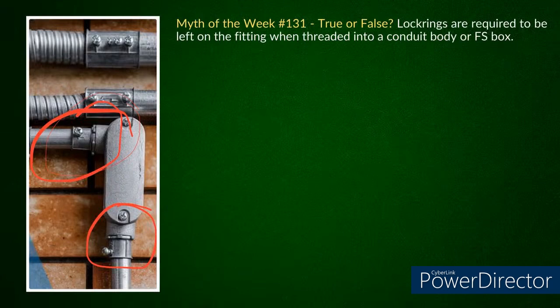And oh yeah, I don't think you'd be passing that over there in Grapevine. No, I can already tell you I wouldn't have passed this. But just from an inspector viewpoint, because I was an inspector, also as a co-instructor, as an author, I would look at this and say, no, lock rings are not required. If your taper threads and everything match up, you're good to go. So that would be my take on it. I just don't believe the lock rings are required.